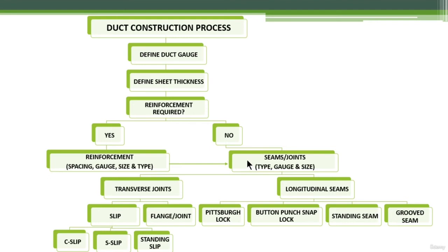When specifying seams and joints, you define their type, gauge, and size. If reinforcement is required, you refer to a table that provides reinforcement details including spacing, gauge, type, and size. Afterwards, you go back to specify the seams and joints of the duct — their type, gauge, and size.